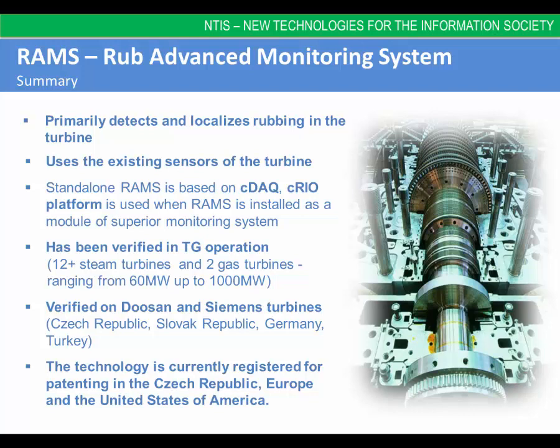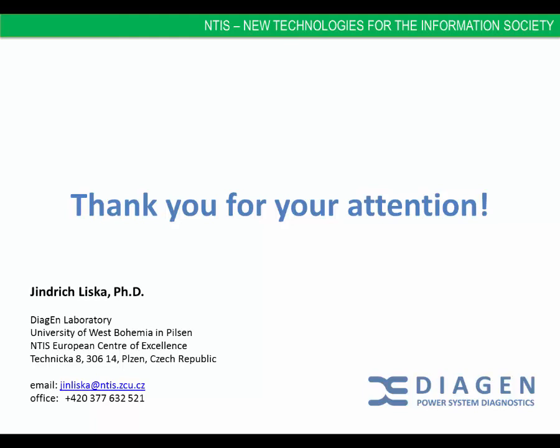The RAMS provides localization of the contact with centimeter accuracy. This fact significantly reduces the duration of forced outage since it is known in advance exactly where the rubbing is. Moreover, planning of repair can be much more detailed for the same reason. From the steam turbine operation point of view, the developed technology serves as an excellent early alert system that prevents steam turbines from wreckage easily caused by rotor-stator contact when not revealed on time. Thank you for your attention.